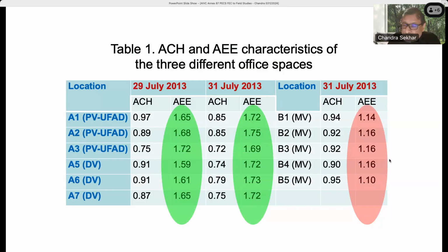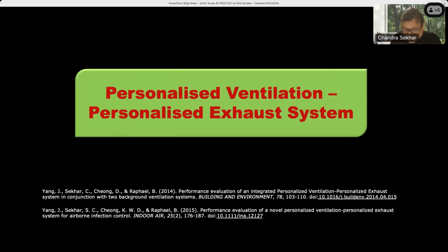Compared to the red shaded zone on the right-hand side, showing the conventional AE values you'd expect—relative to mixing ventilation, which is typically around 1.1 at best, we see 1.6, 1.7 air exchange effectiveness with the personalized ventilation integration.